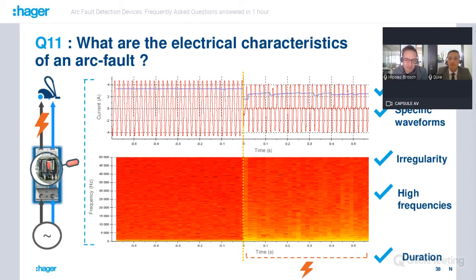Then specific waveforms like current extinction around the voltage zero crossing, as the arc extinguishes itself when the voltage is low. The irregularity of the signal also, because both for the current and for the spectrogram, this is very typical of an arc fault, because the arc is generated in an uncontrolled environment and will burn surrounding materials and therefore modify itself every half cycle. And then the presence of high frequency disturbances, as we can see on the spectrogram, is also a very good characteristic of arc fault, especially when the arc is burning through insulating materials.